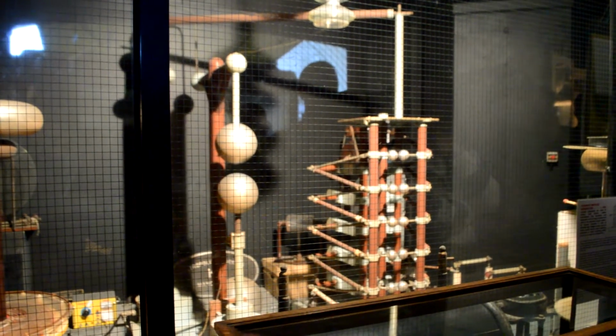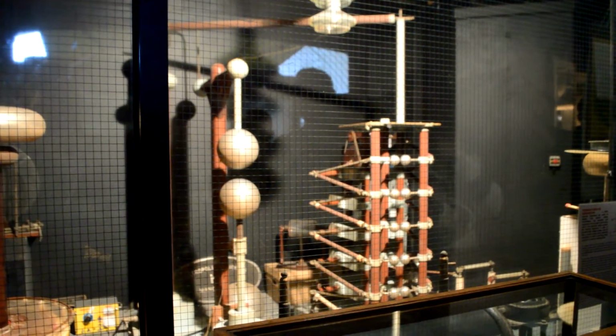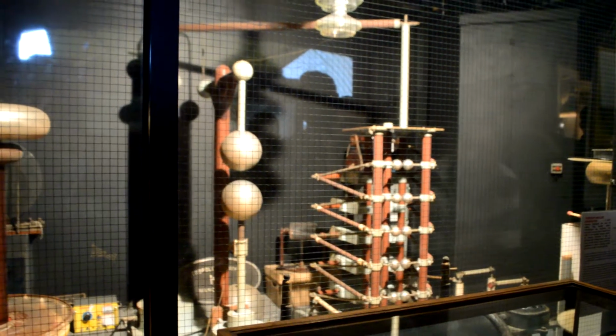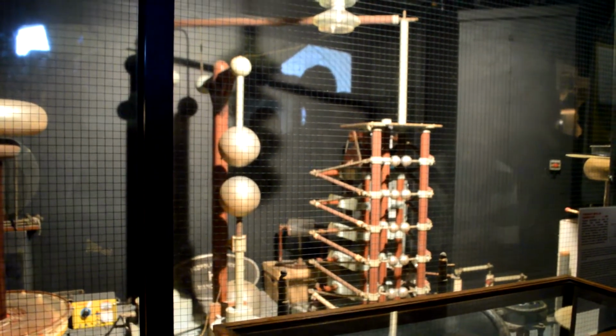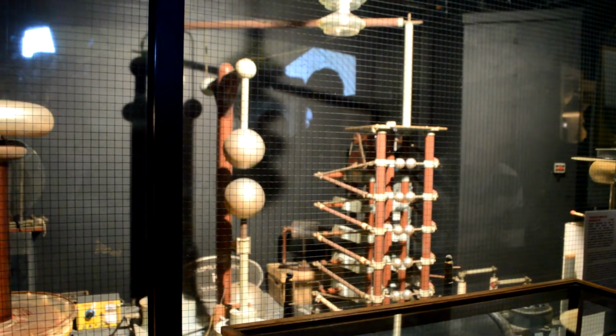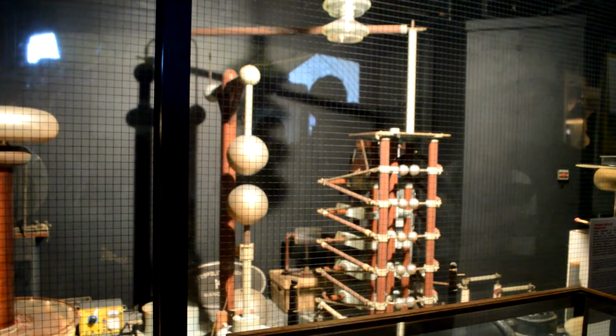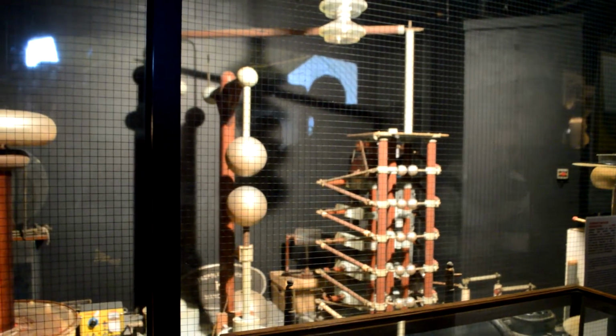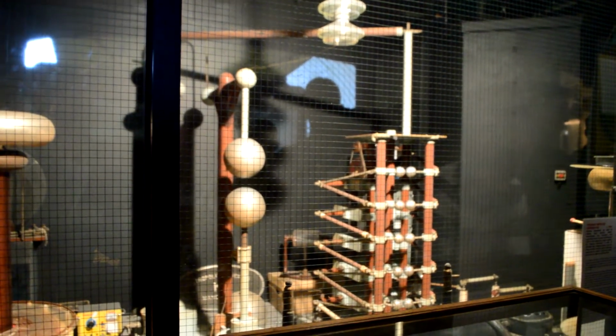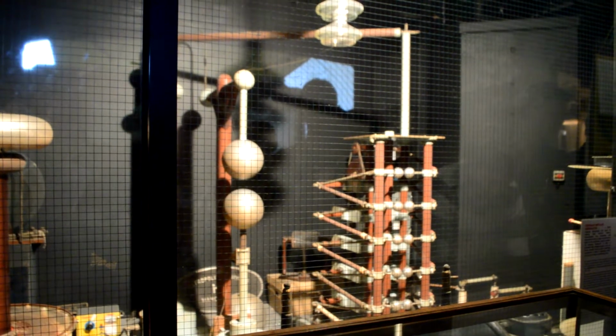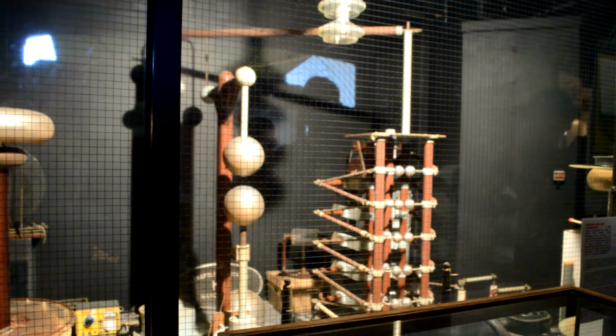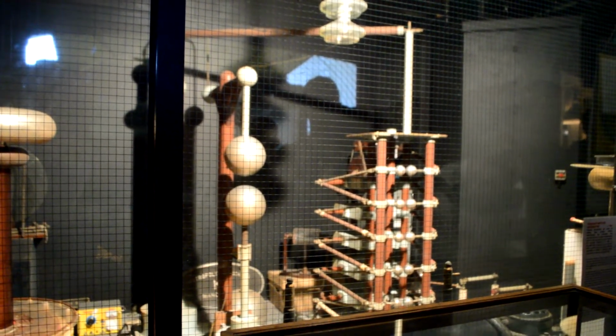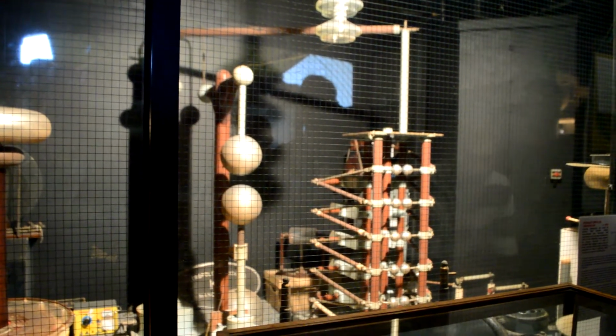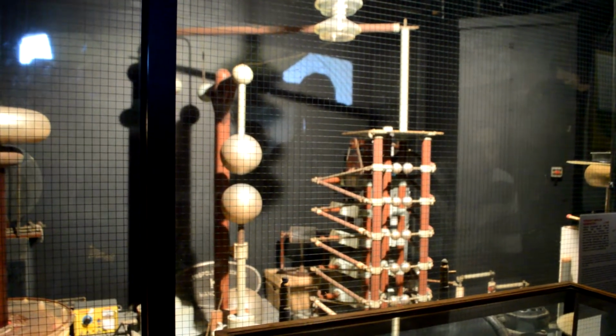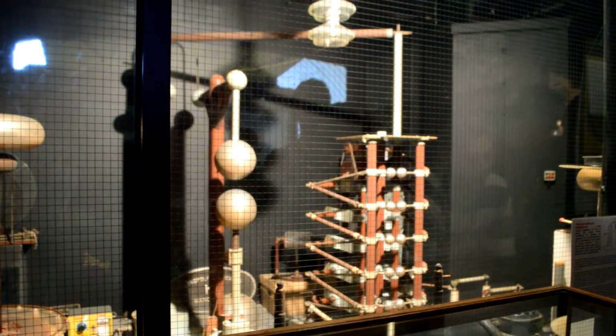In industry, the purpose of this machine was, with a little cleverer control, to simulate a designed rise time and fall time impulse peak discharge, which simulated, if you like, a standard lightning flash. The principle being that when you'd designed your transformer insulation, your cable insulation, your insulator, you would apply, for type approval purposes, a standardized impulse voltage surge to whatever you wanted to test, and it was a pass or fail thing based on the peak voltage applied.